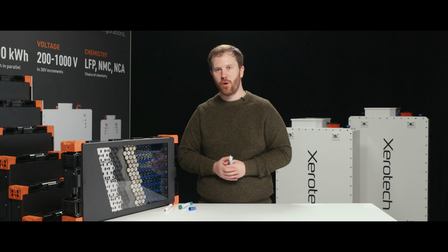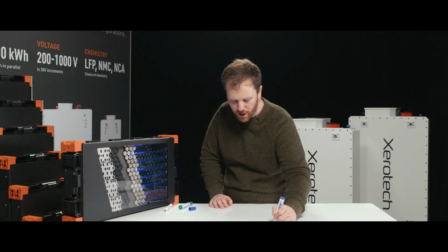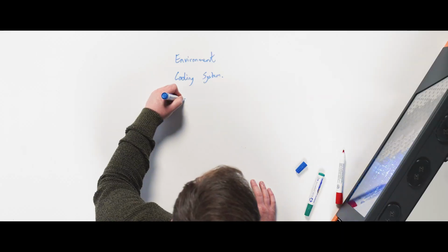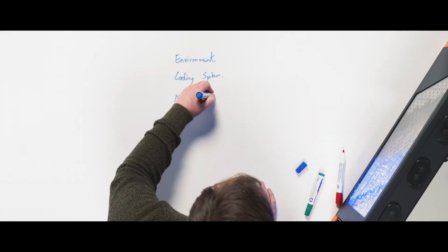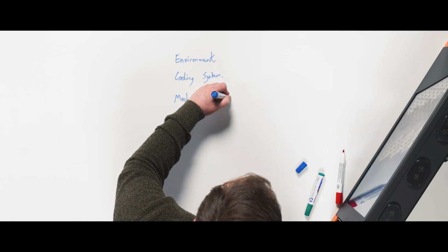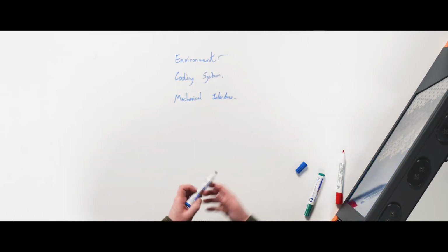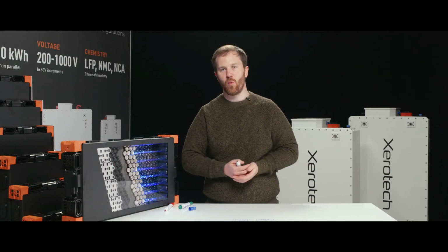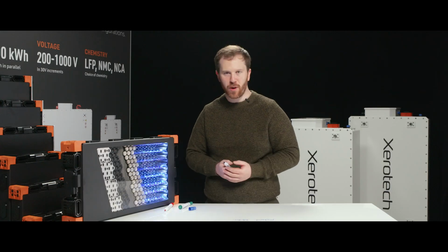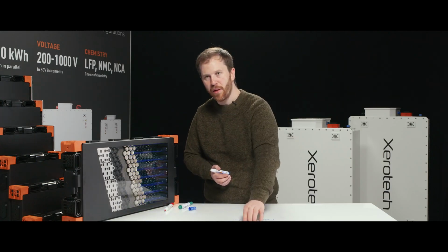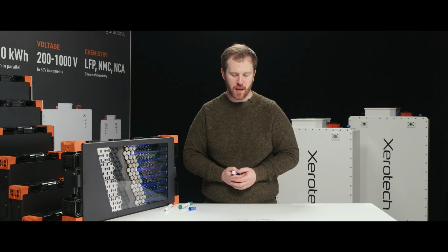So we spoke about some of the things that you can do to a module or to a cell to damage it, but when it comes to a pack, from a safety perspective, you also need to look at that as well. So at a pack level, you have to look at the interfaces of the battery. So you've got the cooling system, you've got the mechanical system, the general enclosure, environmental stuff. So you want to always be looking at environmental, you want to look at the cooling system, and then just the general mechanical interfaces. So from an environmental perspective, temperature, if it's very hot, very cold, if you're exposed to water, dust, dewing points and fog and other things like that, you need to worry about this to make sure that we're not introducing moisture and humidity into the battery pack.